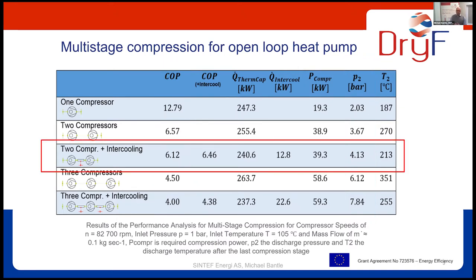We ended up with two turbo compressor stages with intercooling in between, which will lift to a pressure of about 4 point something. So it means that we can reheat our superheated steam to up to 140, 145 degrees from 100. So the dryer will operate with a delta T of around 45 degrees Celsius. And this is basically all simulations. Later on, my colleague from Scanship will tell you how this was realized in real life and where the practical challenges are. Thank you, and back to you, Josephine.